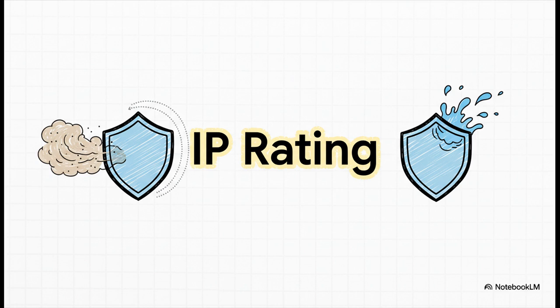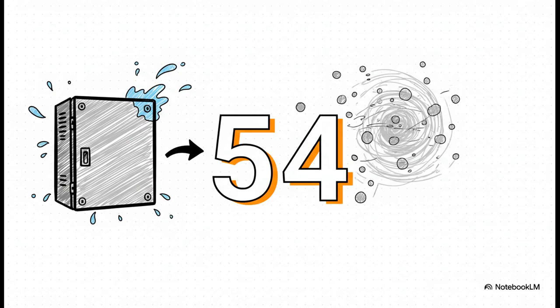Pretty simple: higher numbers mean better protection. For our everyday hero, the grade 304 steel panel, you're usually looking at an IP rating of 54. The 5 means it's really well protected from dust getting in, and the 4 means it can handle getting splashed with water from any direction. It's perfect for most indoor spots.